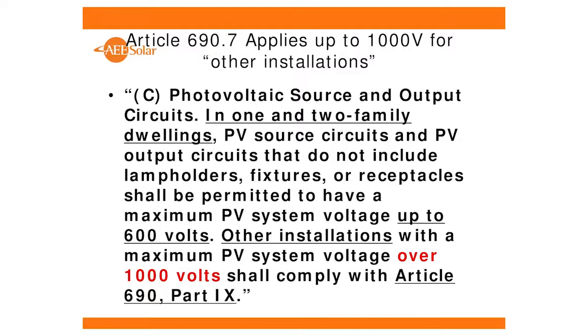Another thing that changed in the 2014 code is to make it specific that systems up to 1,000 volts are actually covered in 690. The way it was written before is anything over 600 volts had to go into Article 490. Okay, so the code in the 2014 code actually had a pretty major revision where a lot of 1,000 volt applications got put into the low voltage category.